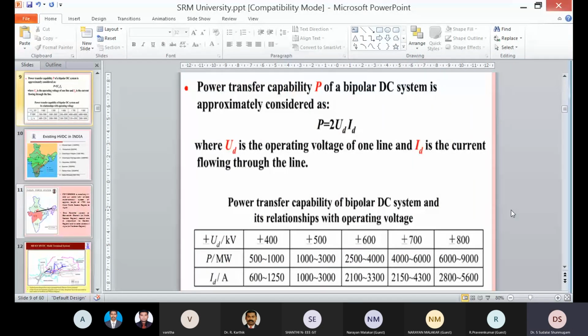Similarly, when it comes to the power transfer capability of a DC system, I have shown only a bipolar system. I have not shown a multi-terminal HVDC system. For a bipolar HVDC transmission system, the power transfer is limited by 2UI, where U is the system voltage and I is the approximate current carried. I have shown up to plus or minus 800 kV. What should be the current range? What should be the power range? If you want, I will be sharing the PPT. You can look into the formula later.